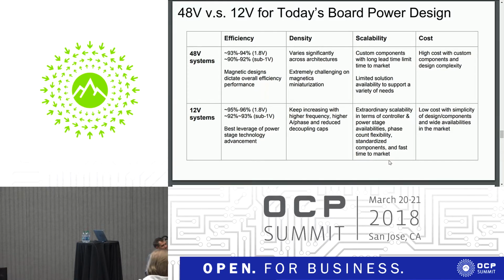I think the one reality we're seeing is power increasing very fast on all these data center machines. A couple years ago your server was still talking about 160 watts per CPU socket, and today you're seeing a lot more 300 watt designs and processors. You're absolutely right - if you still stick with 12 volt infrastructure for the rack, you're probably seeing a challenge where you have to remove some machines from your rack. You cannot fully populate your rack, and the problem is taking off enough heat from the rack level.